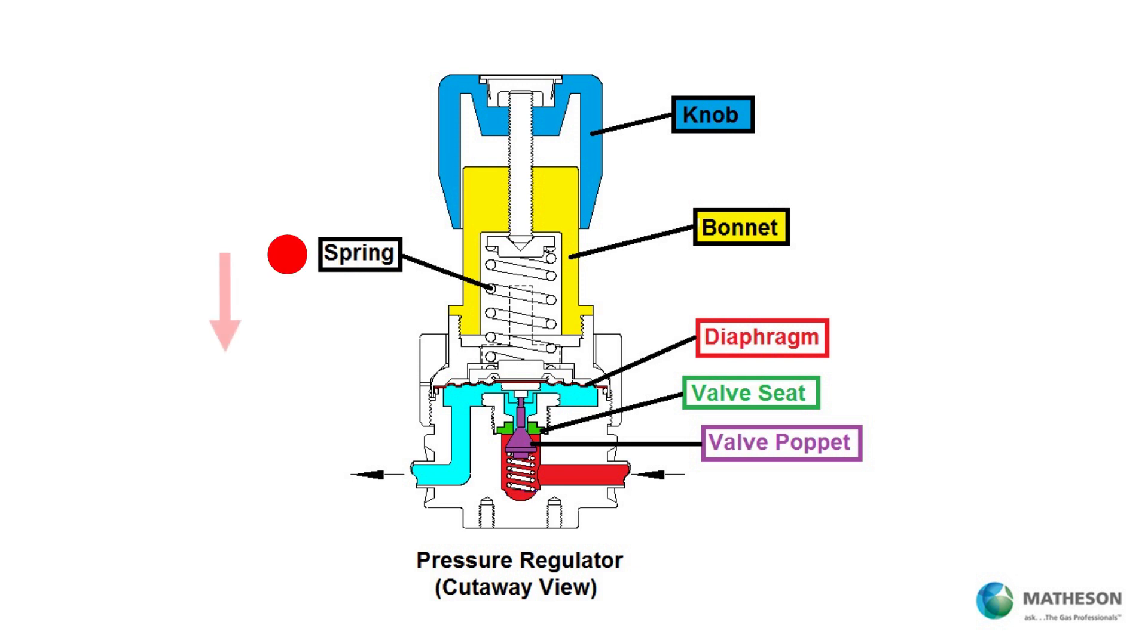When the spring is compressed, the spring displaces the diaphragm which pushes on the valve poppet, causing it to move away from the valve seat. The orifice becomes larger in order to provide the pressure and flow required. Increasing gas pressure under the diaphragm will push up on the diaphragm, allowing the valve poppet to close against the valve seat.